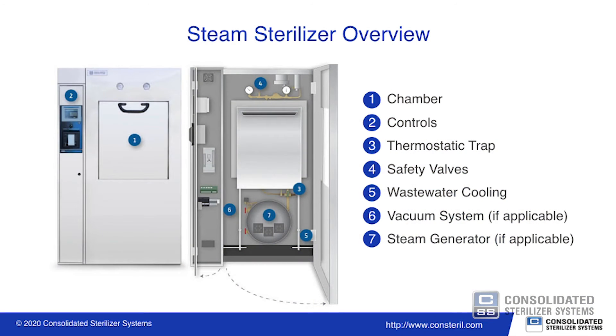A typical laboratory autoclave includes the following components. The vessel, which is the main body of the autoclave and consists of an inner chamber and an outer jacket. The control system, which is operated using a controller interface, not unlike what you'll find on a microwave or oven, albeit more complicated. A thermostatic trap, or steam trap, which allows air and water condensate to escape from the chamber. And a safety valve, which is the final fail safe for the pressure vessel.